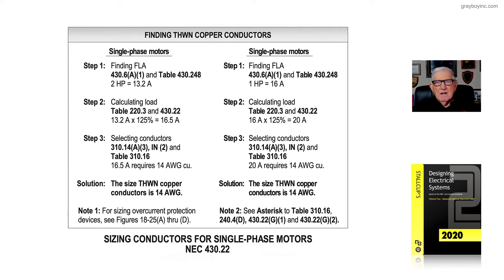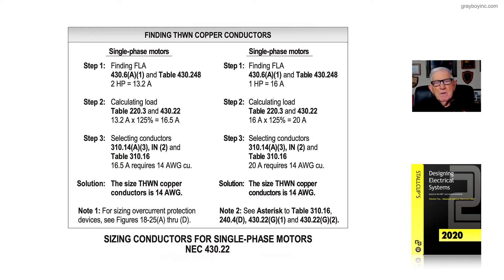Some designers call that item 2. After the calculation of 125% times the full-load current rating selected from Table 430.248, we use that total amp rating to go to Table 310.16 and select our conductors.